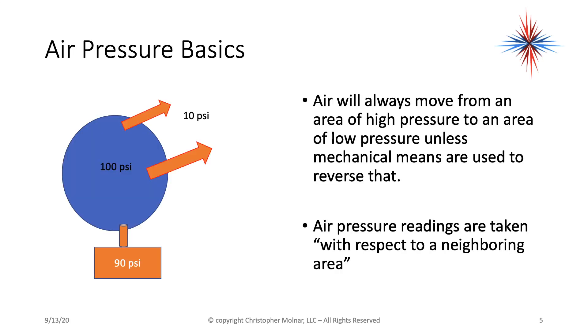Let's review some air pressure basics. Air will always move from an area of high pressure to an area of low pressure, unless mechanical means are used to reverse that — in other words, a fan or blower motor. Air pressure readings are always taken with respect to a neighboring area. For example, if I have 100 psi inside a ball and 10 psi surrounding it, the reading will be 90 psi. It's a comparison reading.